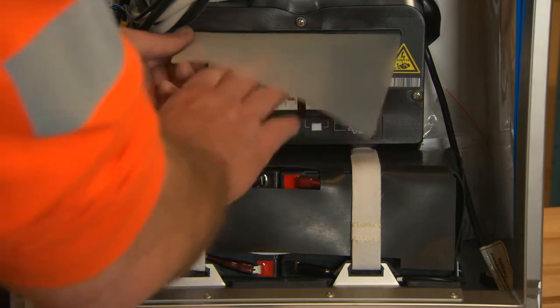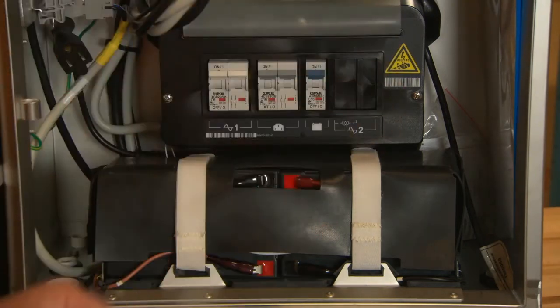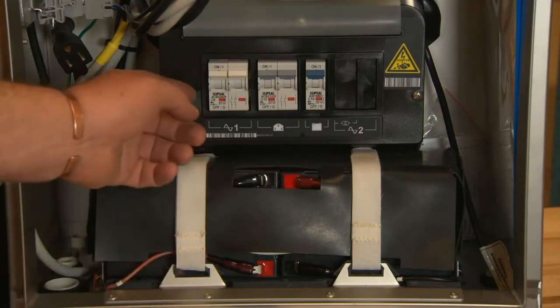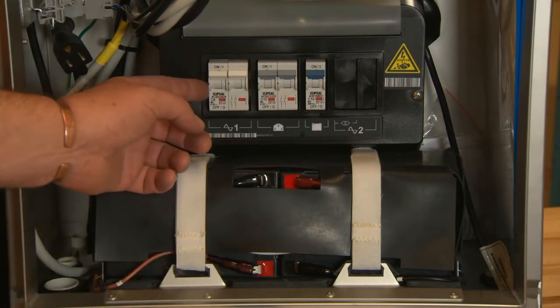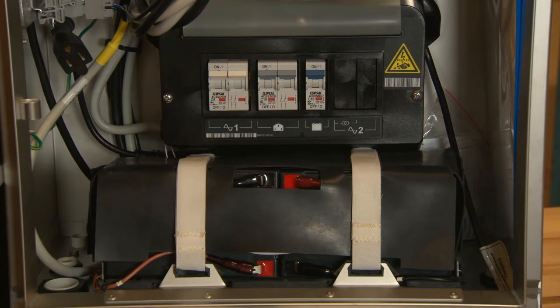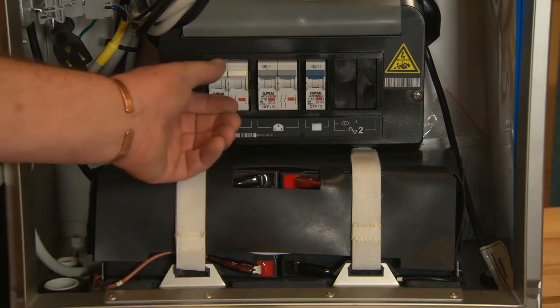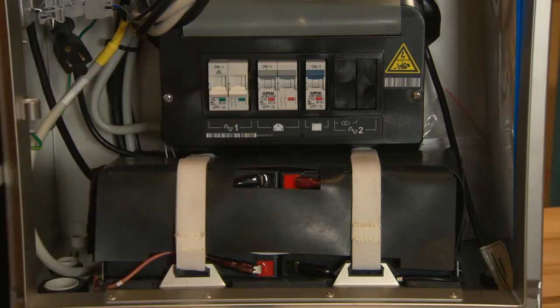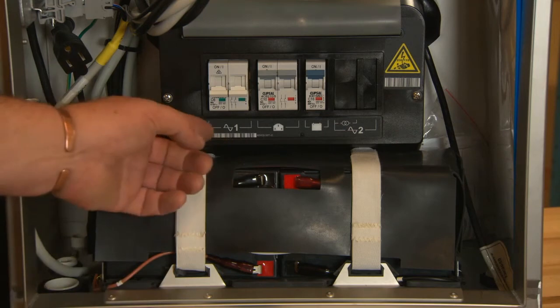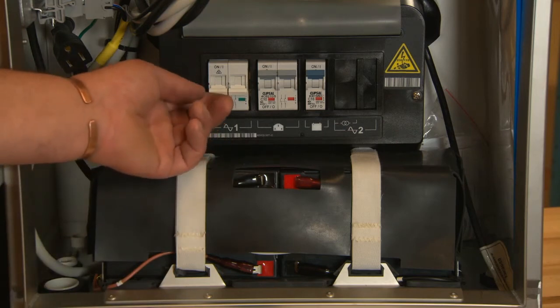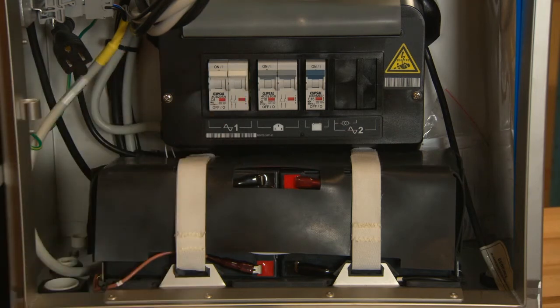On the bottom of the unit, below a plastic flap, are 3 supply breakers. The first breaker on the left-hand side is the AC supply breaker. If the AC power has been turned off on the above display, check your breaker. It should be in the down position. To test this, switch it to the up position.